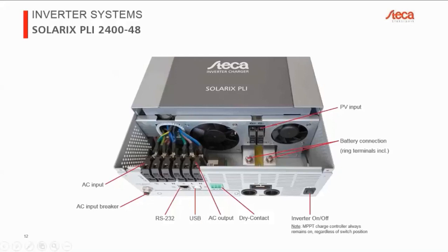Then we have a serial RS-232 connection for data. If you need the protocol, you can request it at Steca. We will send that out to you. Also for USB, also for data. Then we have the dry contact, the relay contact, which is typically used to start generators, for example, or to signal when you require power, basically.